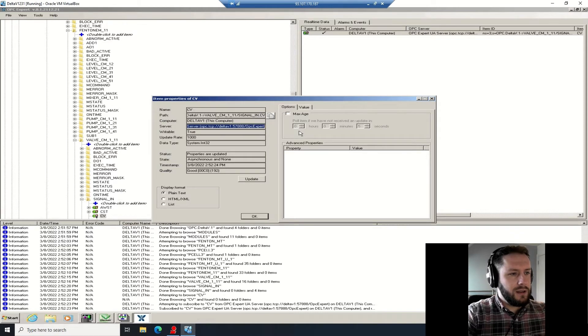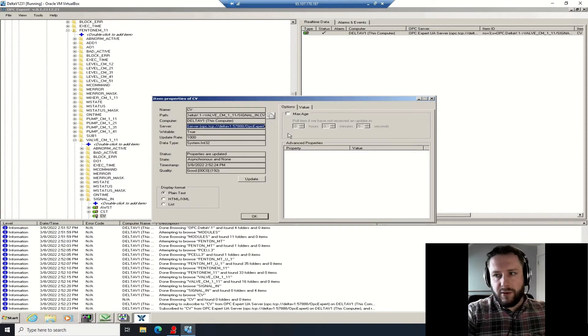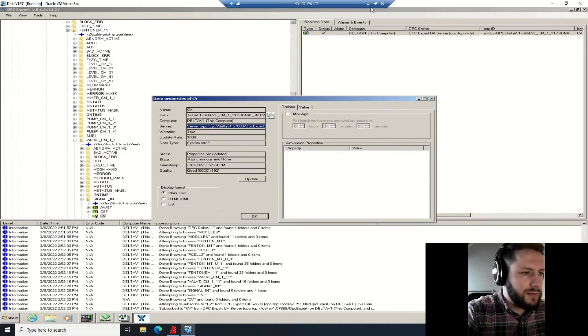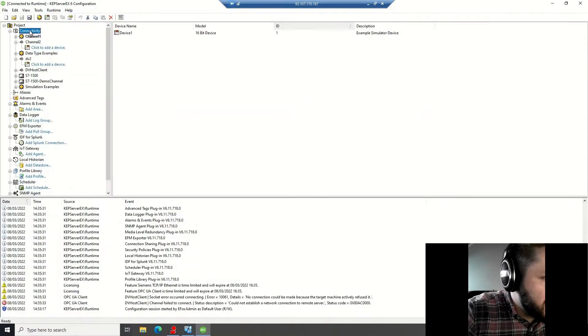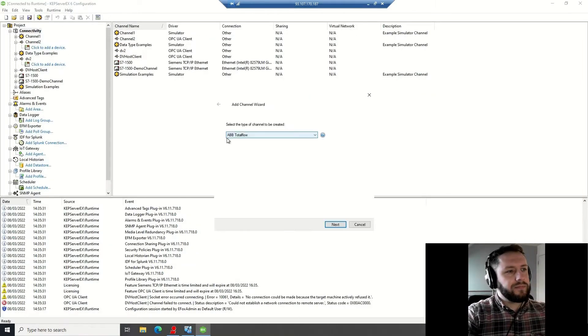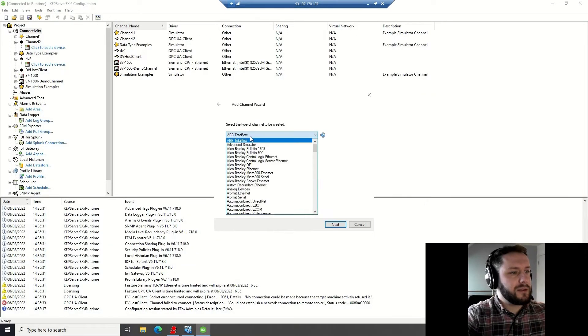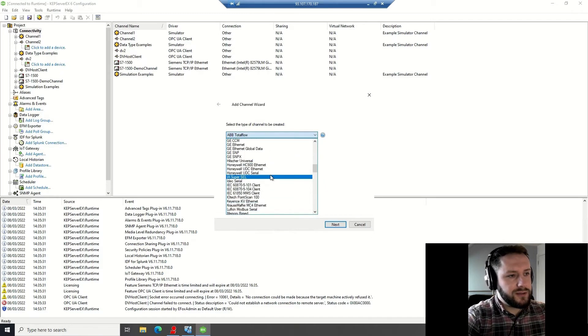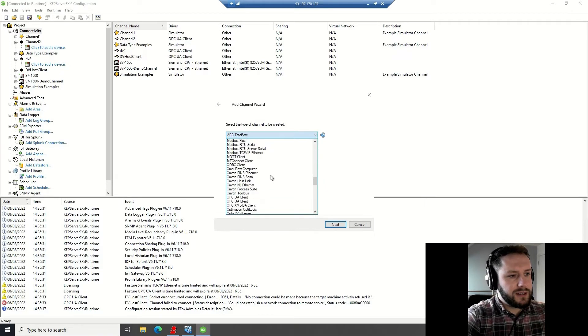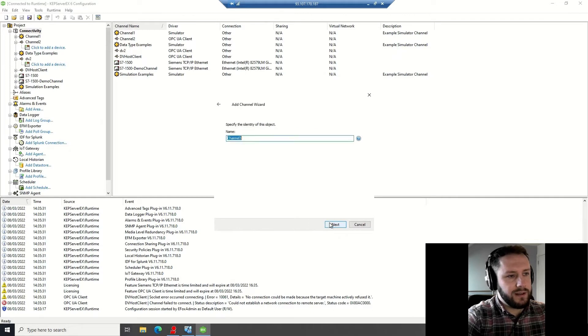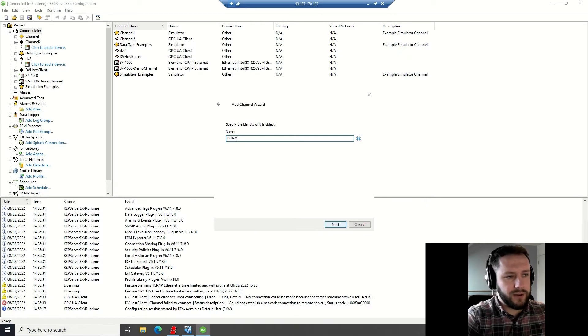Which was pointed out just a few seconds ago, which is from the TCP forward slash DeltaV1, which is the name of the node, and then the port address of 57888 forward slash OPC Expert. So coming back to Kepware on your host machine, you want to select the communications type, the channel type, to be OPC UA Client. Next, name it appropriately - I'm just going to call it Delta V demo channel.